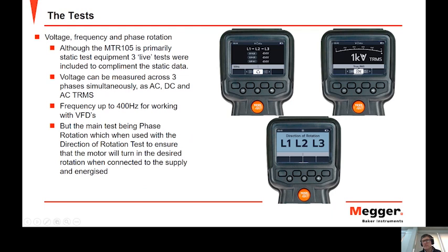Frequency can be displayed up to 400 Hertz. And then we also have our phase rotation test, and that will indicate the power supply's phase rotation, L123 or L321. And that will help us when using the motor rotation direction test later to ensure that when we start the motor, the shaft will turn in the correct direction. We'll have a physical demonstration of that.